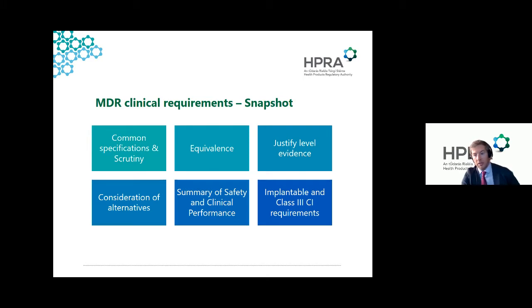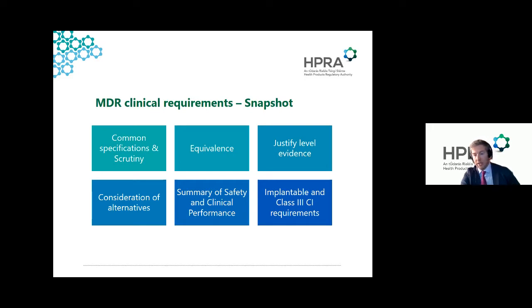While it's not possible to detail all the changes MDR brings from a clinical perspective, here is a snapshot of important ones. Common specifications are an important new rule in MDR allowing creation of specific rules for clinical or technical aspects of medical devices. The scrutiny procedure — or clinical evaluation consultation procedure — is a new type of procedure involving independent experts. Equivalence requirements are now brought into law for the first time in Annex 14 of MDR, with all characteristics and individual criteria for the clinical, technical, and biological aspects of equivalence.